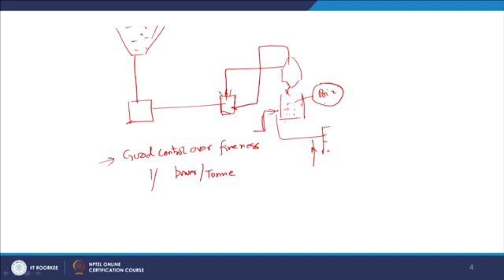Now, we will further discuss the burners which are used for burning the pulverized coal. The main function of the burner is to burn the fuel, and a good design of burner indicates that the proper flame shape and flame travel are maintained, and the ignition is stable. Ignition should remain stable inside the burner, and there should not be any flashback. To prevent flashback, the forward movement speed of pulverized coal should equal the flame front speed. If these two speeds match, there will not be any flashback. If the feeding speed of the coal is less than the speed of the flame front, flashback will take place, and that should be avoided.